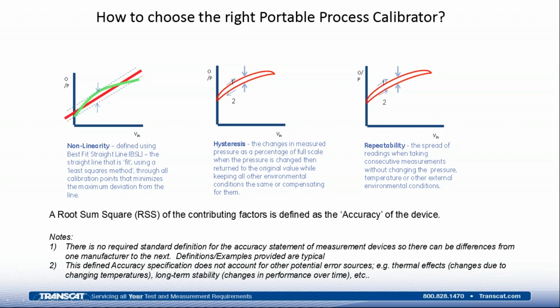Hysteresis is the difference in a given output for a given input when the variable is applied in an increasing and decreasing direction. So, for example, if we applied pressure to a gauge or a pressure sensor, and then we release that pressure, there may be some difference in the measurement at a given pressure point. And we define that as the hysteresis of the device.